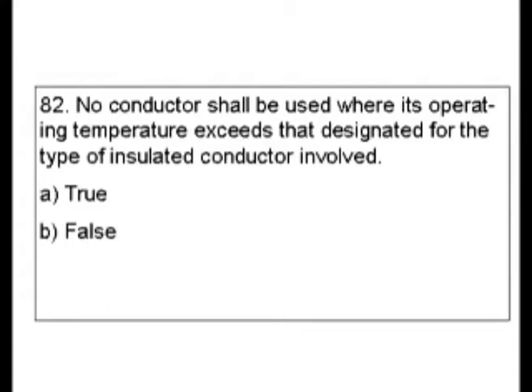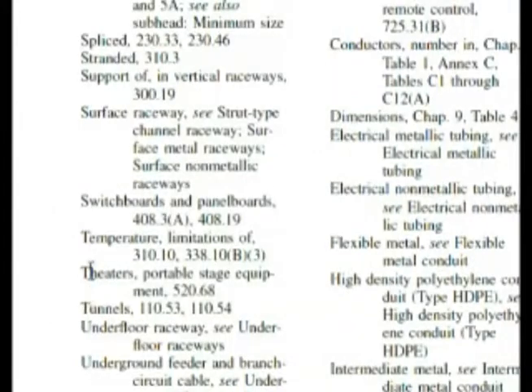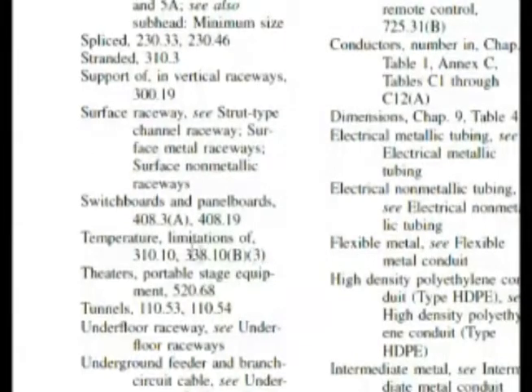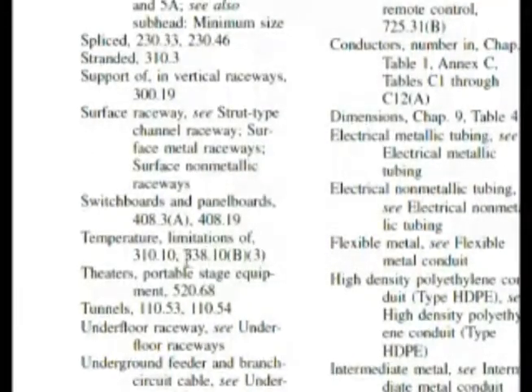Let's find the exact answer in the codebook. The keyword we would look for here would be conductors, but let's see if we can find something about temperatures and conductors. Under conductors and the subheading we find temperature limitations. We're given the choice 310.10 and 338.10b3. I've said before if I have this detail I'd like to go there and see if I get lucky. In this case, let's choose 310.10.